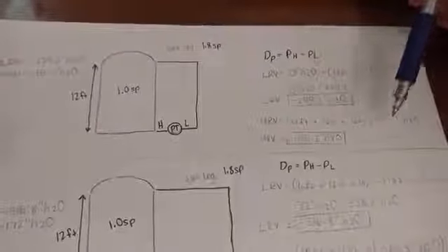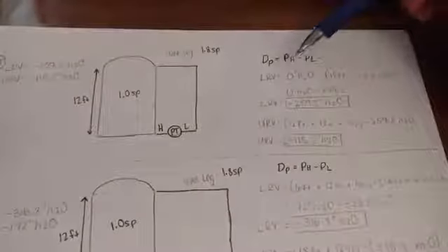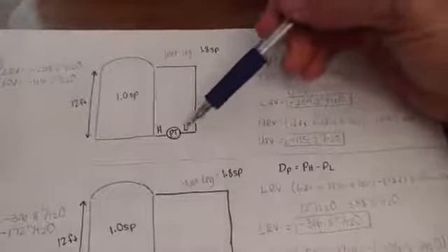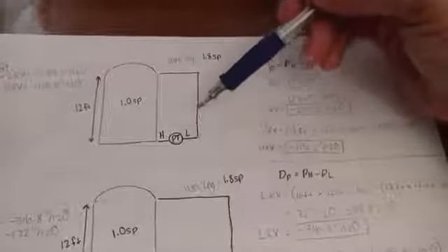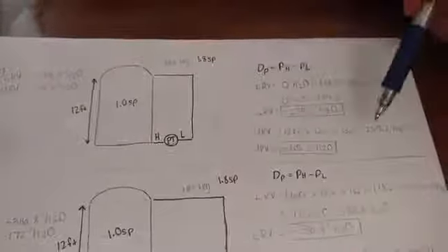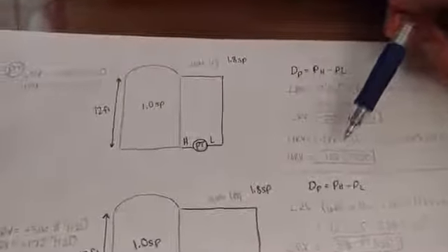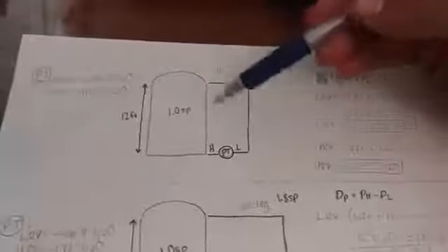And we're going to subtract it from our pressure low, which is what we just calculated over here, that is 259.2, and when we subtract them we get negative 115.2 inches H2O.